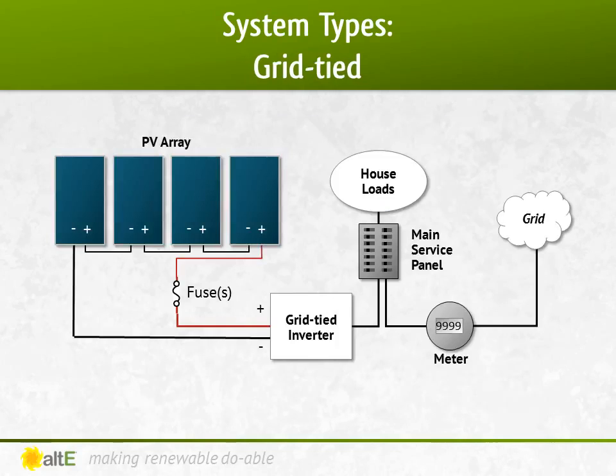In a grid-tied system, the solar panels are wired through fuses to a grid-tied inverter. The inverter is wired to a new breaker in your main AC panel. The electric company may require you to switch out your power meter to a bi-directional meter, which can spin backwards when selling power and forward when buying. This is known as net metering.